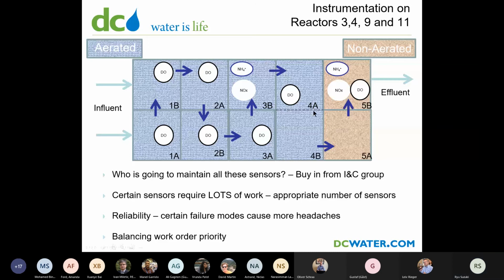Especially the DO probes and NOx probes have been relatively reliable, but the ammonia probes are a huge pain. It takes full buy-in from a strong instrumentation and controls group to stay on top of it. And not just the sensors, but also to make the control successful, you have to stay on top of all your actuators, airflow meters, and the hardware and software of your controllers. Those all have to work really well.